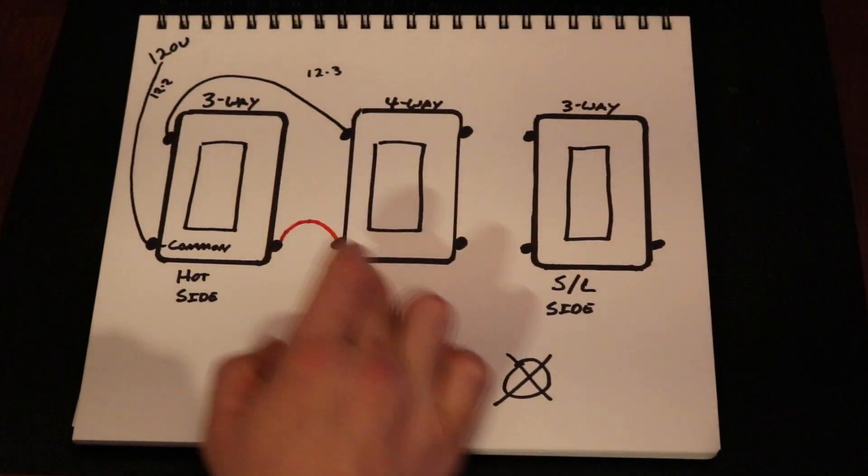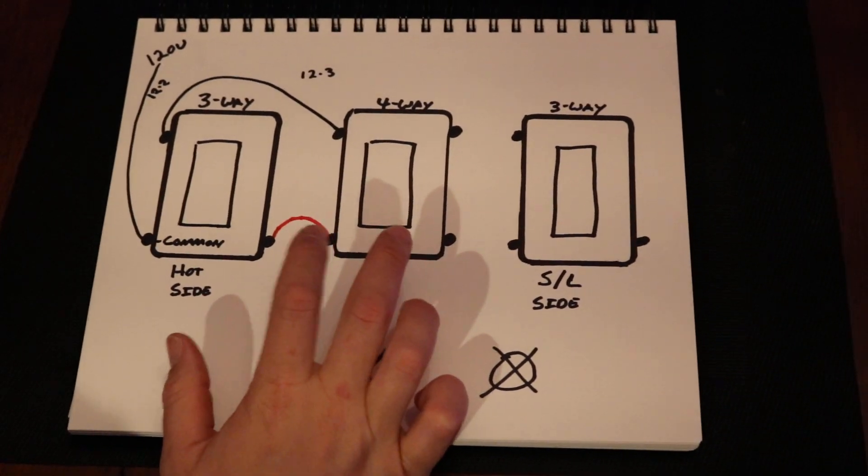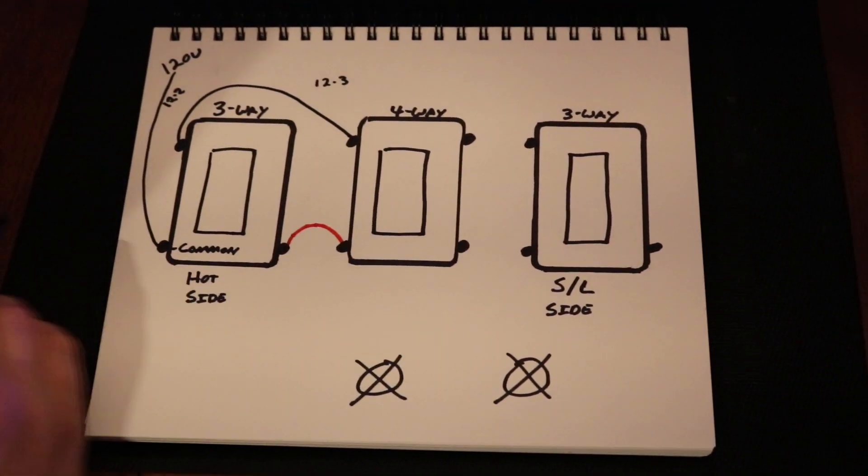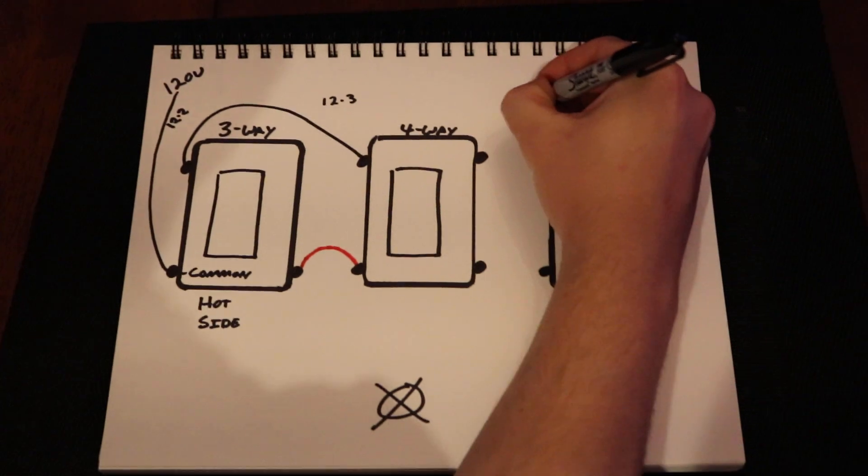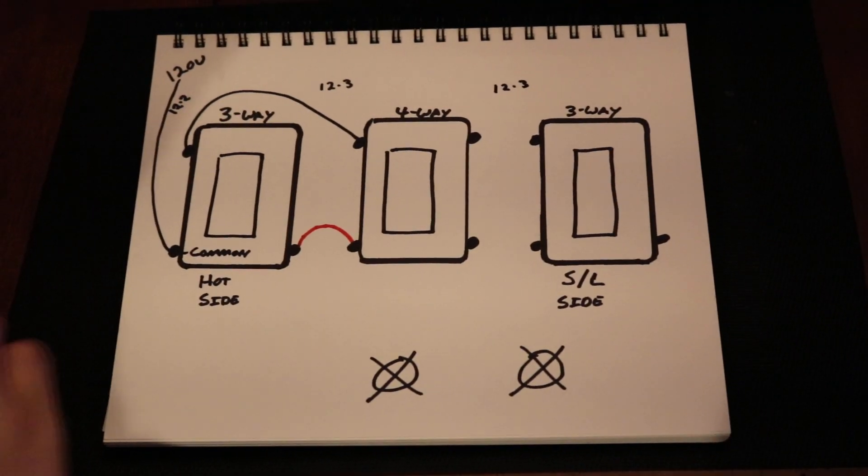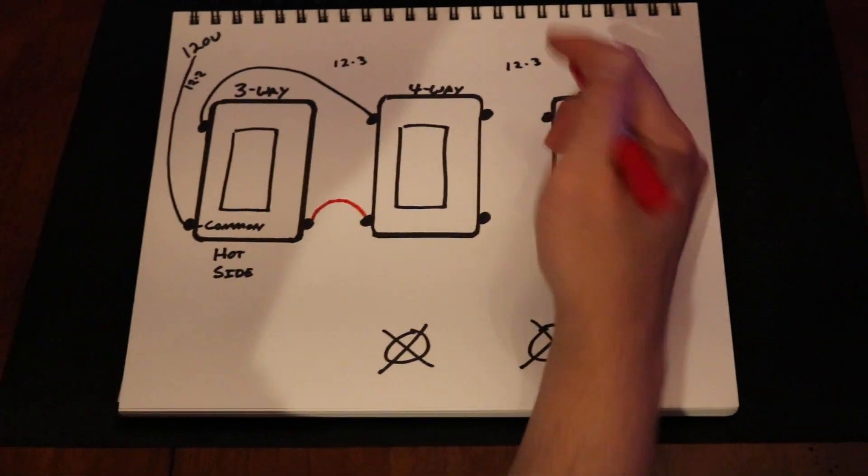You're going to have two conductors going from your hot side to your four-way location. One way to wire a four-way switch where it's foolproof, it'll never be a problem, it'll work every time: you have your incoming travelers, your two conductors. If you put them on one side of the switch, where here we're putting it on the left side, and the travelers that are outgoing, let's just say 12-3, pretend we're doing it in a residential.